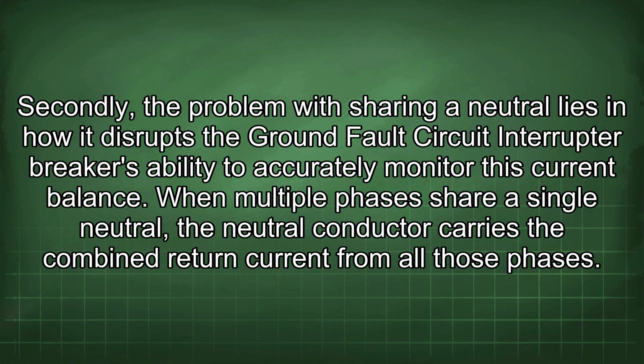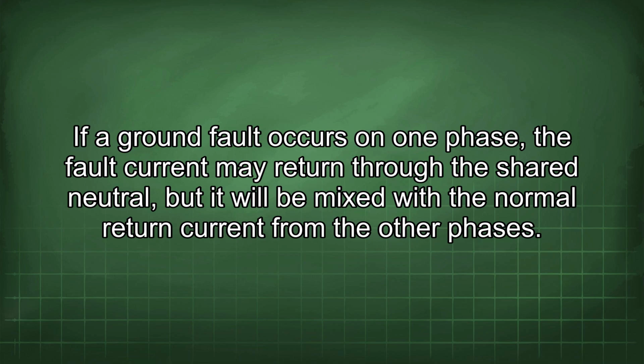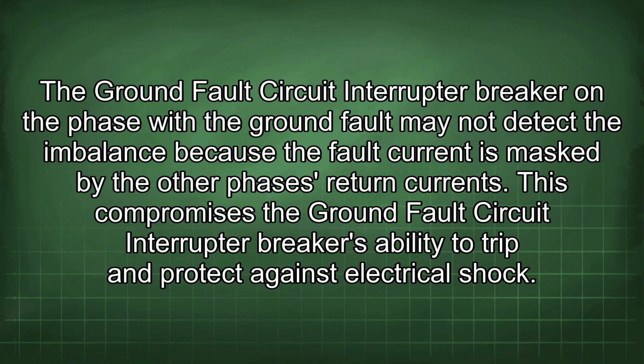Secondly, the problem with sharing a neutral lies in how it disrupts the ground fault circuit interrupter breaker's ability to accurately monitor this current balance. When multiple phases share a single neutral, the neutral conductor carries the combined return current from all those phases. If a ground fault occurs on one phase, the fault current may return through the shared neutral, but it will be mixed with the normal return current from the other phases. The ground fault circuit interrupter breaker in the phase with the ground fault may not detect the imbalance because the fault current is masked by the other phase's return currents. This compromises the ground fault circuit interrupter breaker's ability to trip and protect against electrical shock.